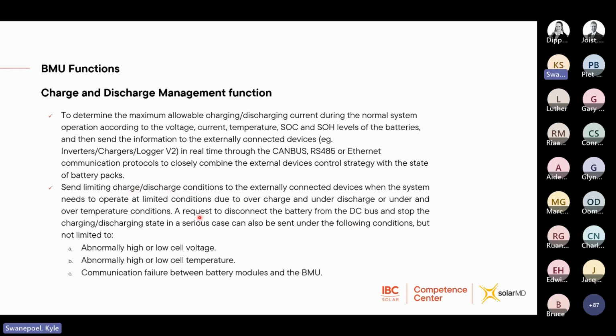All right. And if these requests are not met from the inverter side, if it continues to charge and it's overcharging the battery or under discharging, the battery will disconnect itself from the DC bus, and this will be under high or low cell voltages, high or low temperatures, or a communication failure between the battery modules and the BMU. So it's just another protection step that is built into the BMU, that if it loses communication with any one of its battery modules, it will disconnect itself from the DC bus because it doesn't know what's happening with that battery module in its stack.